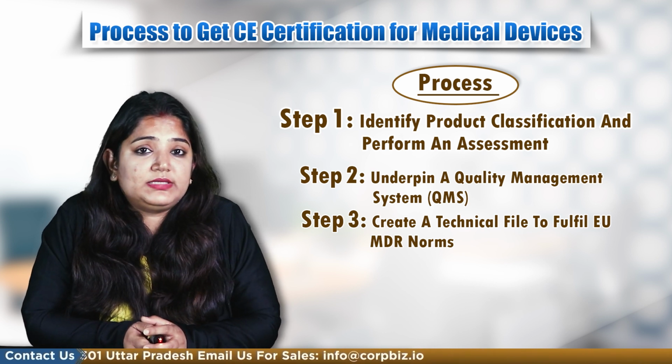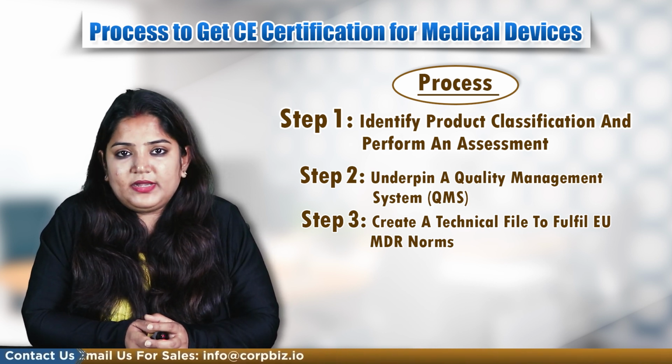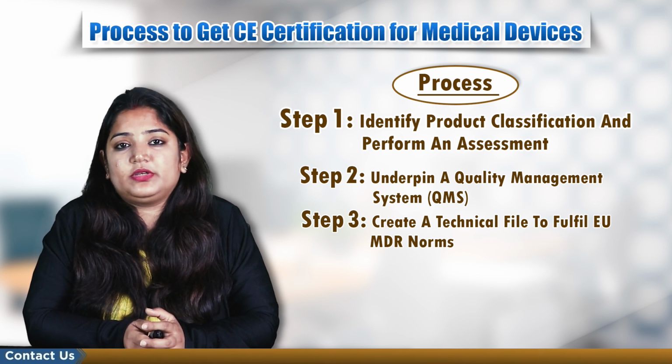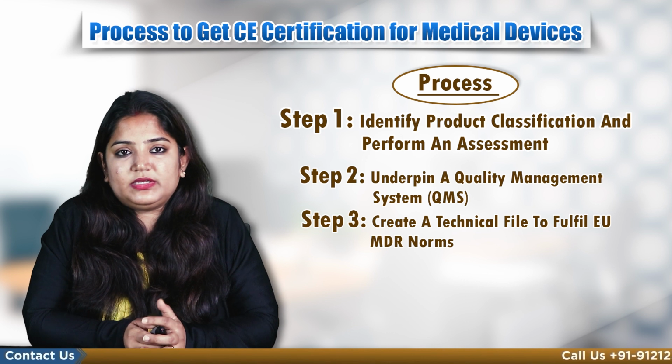For a class 3 device, a design dossier should be prepared and it must enclose data from the technical file and the design process concerning the medical devices.